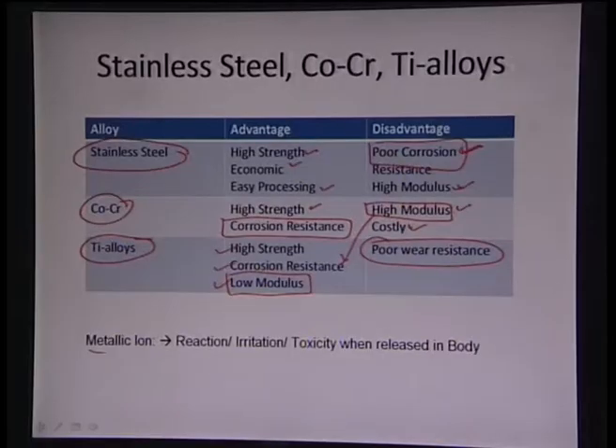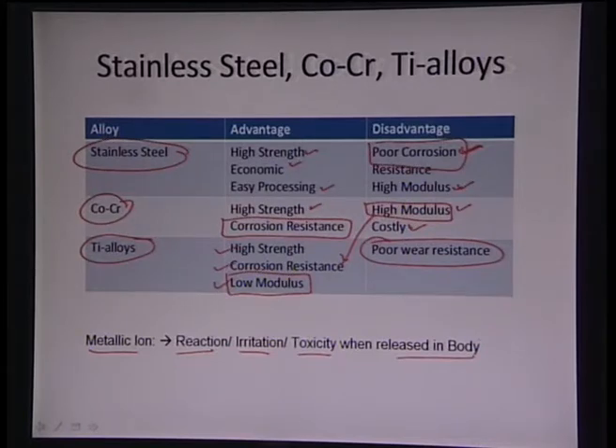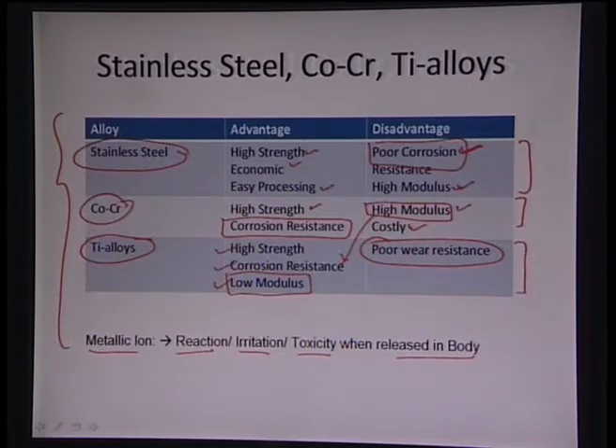This is a very vicious cycle: either the implant material has very poor corrosion resistance, or very high modulus, and once they have very low modulus, the problem becomes handling the wear property of those alloys. Always we require a combination of certain materials — one single material cannot take responsibility for all the functionality expected of it. The release of metal ions can induce reactions with the body, cause irritation, or even be toxic, so all these aspects have to be considered while designing a biometallic material.